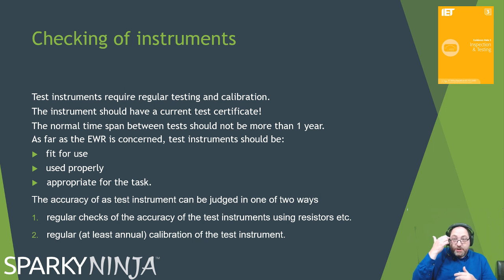Something that will be mentioned a lot is checking your instruments. Instruments require regular testing and calibration. They should have a current test certificate. The normal time span is a year, which is kind of an unofficial rule. What you need to do is ensure the equipment is fit for use, used properly, stored properly, and appropriate for the nature of the work it's going to be doing. The two ways we can often do this: regular checking of instruments using resistors or check boxes or pre-check boxes, or annual calibration.